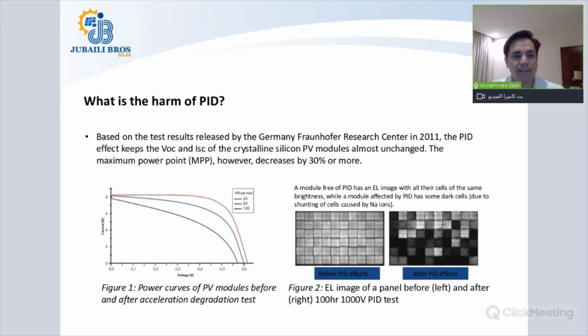As you can see in this graph on the left side, normally the IV curve of a solar PV module is shown in the red line. With the potential induced degradation effect, this will be shifted more and more as time goes. If such a PV module is tested before a PID degradation happens through an electroluminescence test, all the cells in the PV module will have the same brightness as shown here.